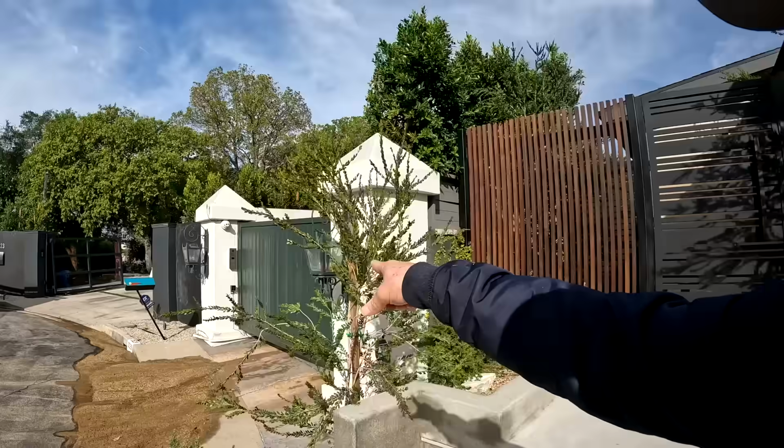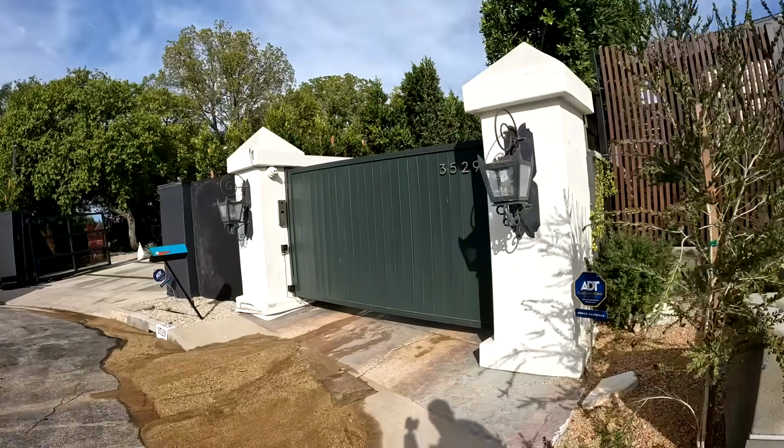48 hours later, we got confirmation from the city that it is an aquifer underneath that courtyard, guys. Amazing journey this leak has been. Out of my 32 years of experience of doing this, I have never had to go through the process of elimination, nor have I ever seen so many leaks in a neighborhood. So through this process, we not only solved Donna's, but we also solved all the other neighbors that were having extreme water bills that they had no idea about within that 30-day billing cycle.